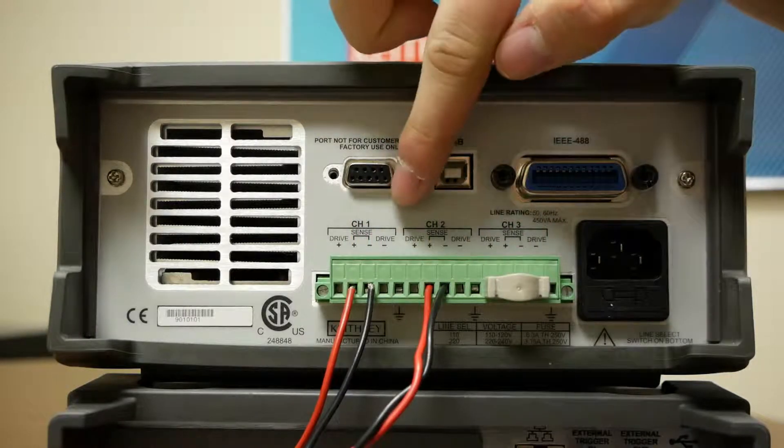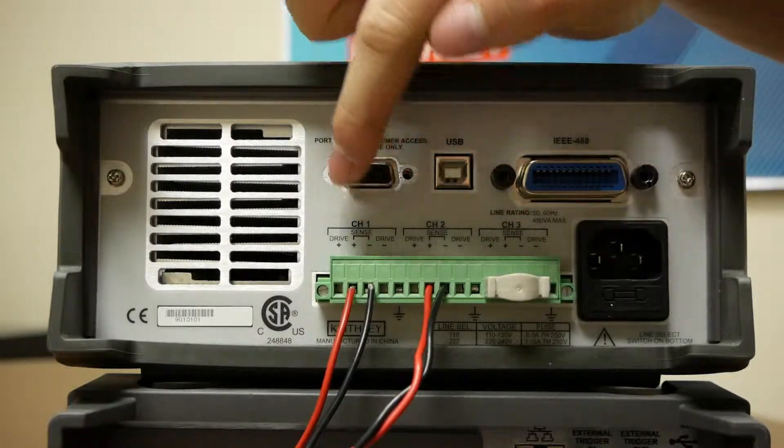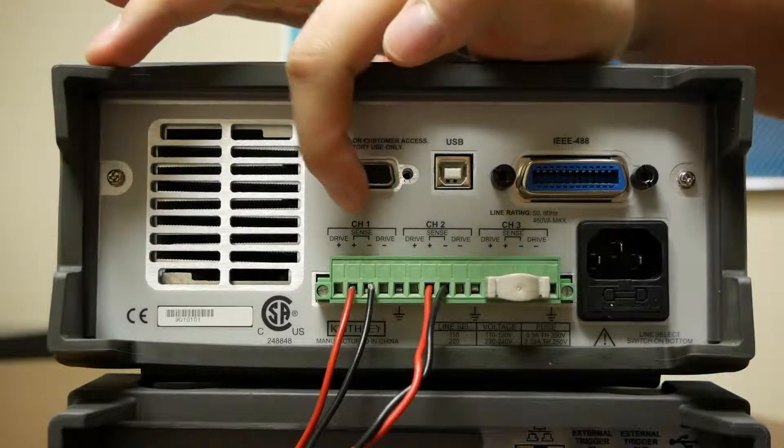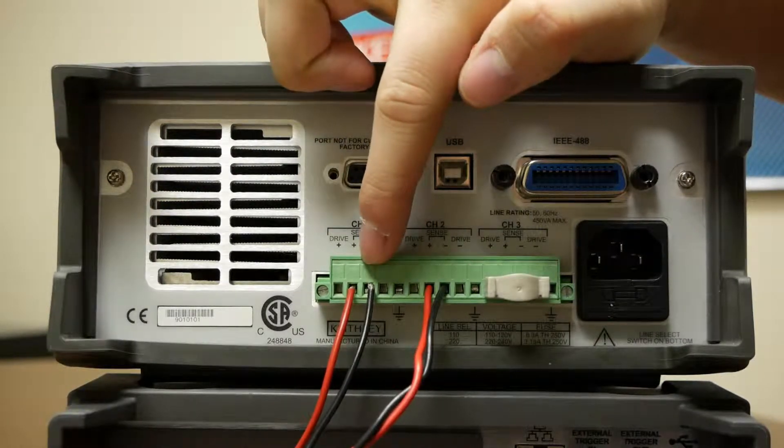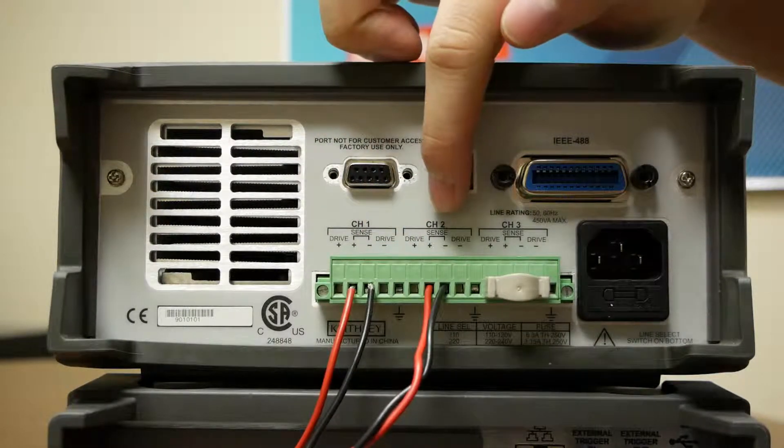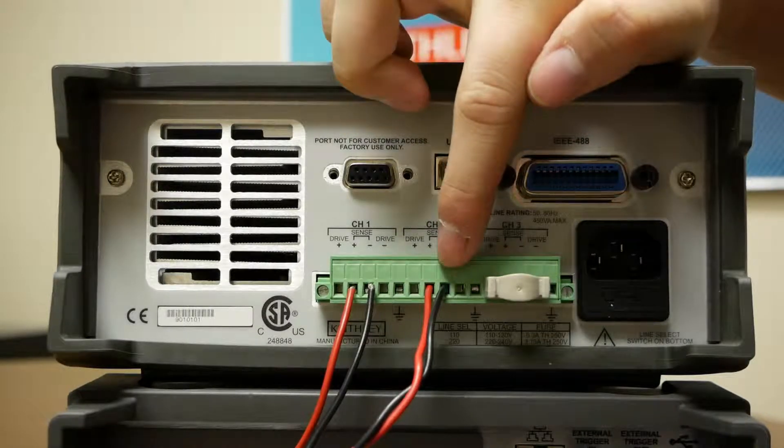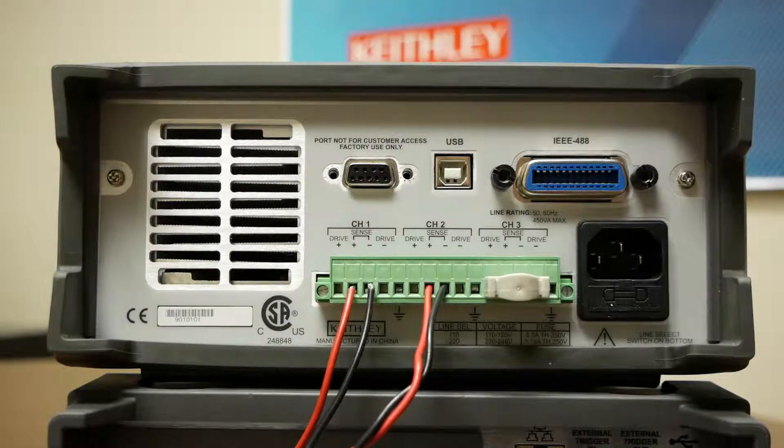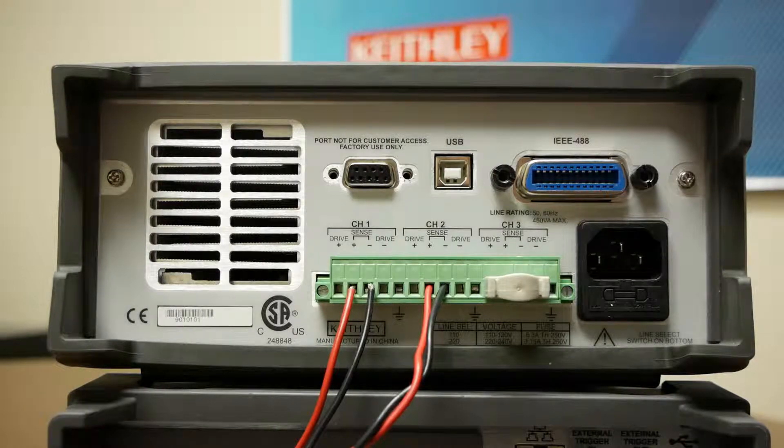our connector is going to line up with our channel configurations and we will connect sense high and sense low on channel 1 here directly out to the DUT and our channel 2 sense high and sense low here directly out to the DUT. This will give us an improved voltage monitor for our test.